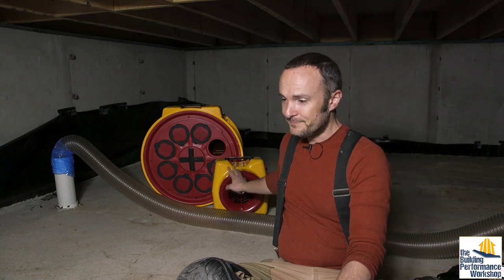I have the 300 model. Even at wide open configuration, I can only get 800 CFM. And I was going to run like 300 CFM to get me to 10 pascals.